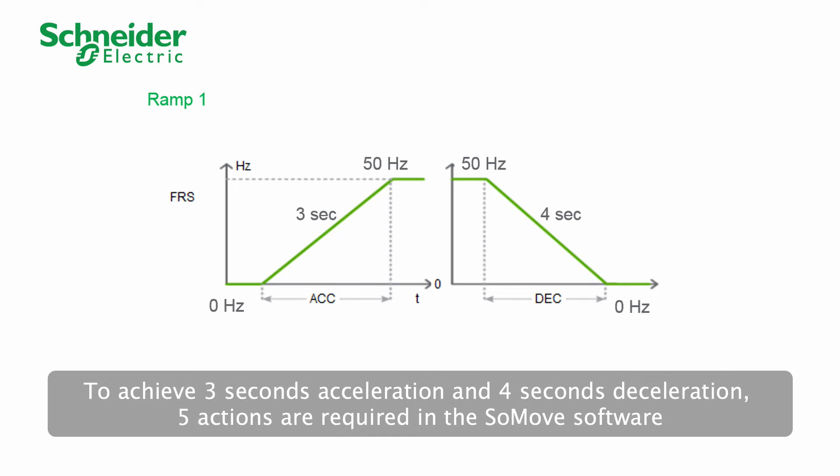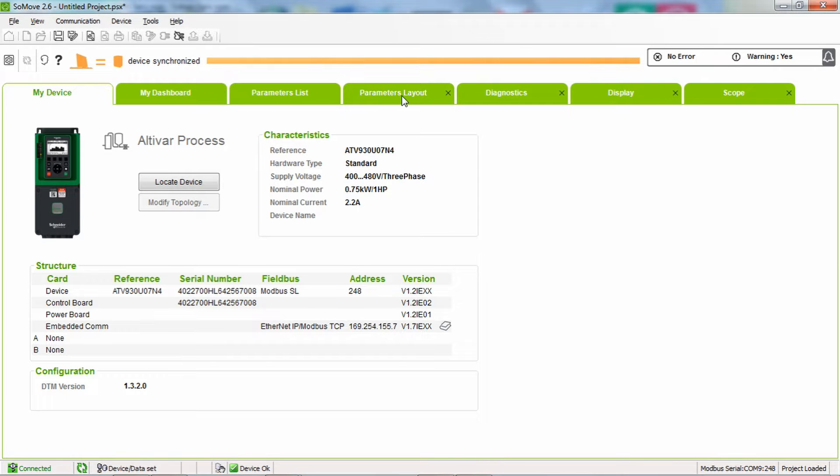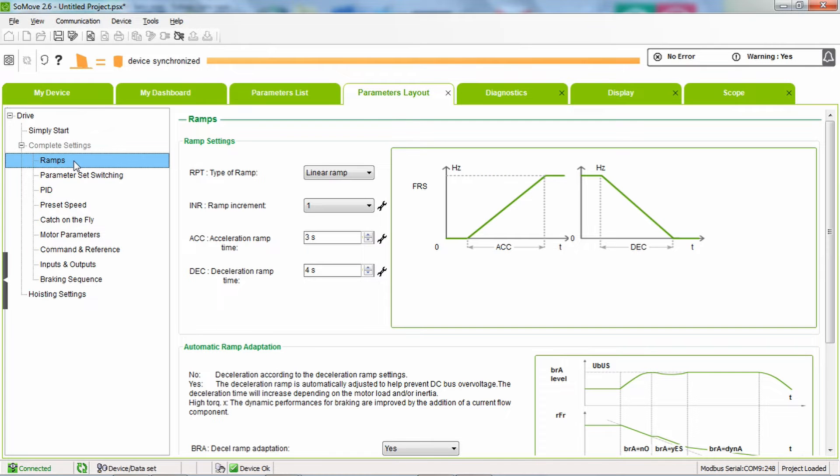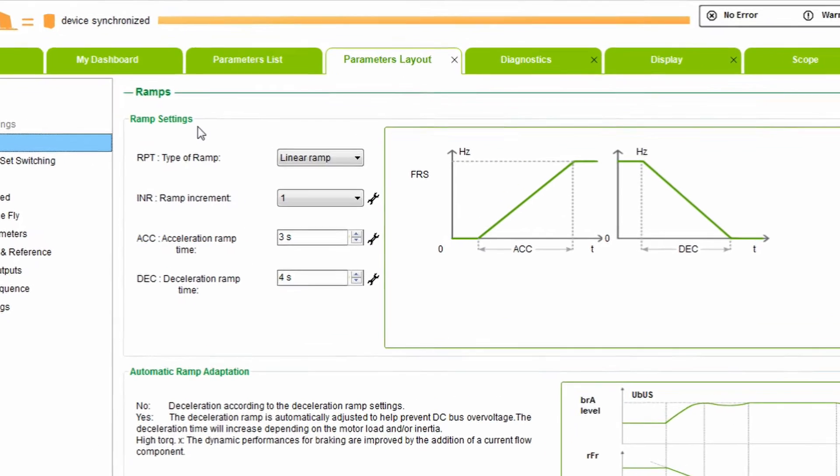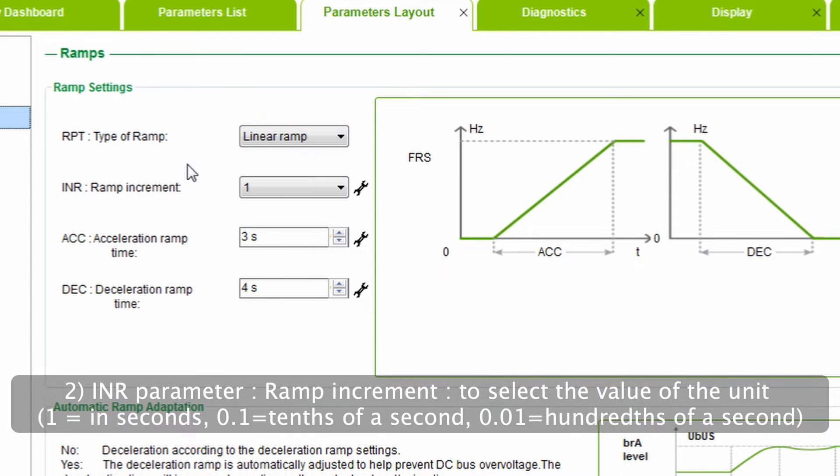To achieve three-second acceleration and four-second deceleration, five actions are required in the SoMove software. Number 1: RPT parameter. This is the type of ramp. In our case, we will use a linear ramp.